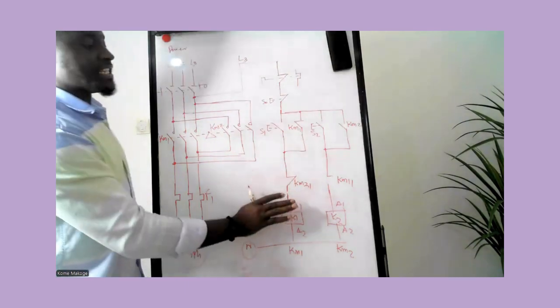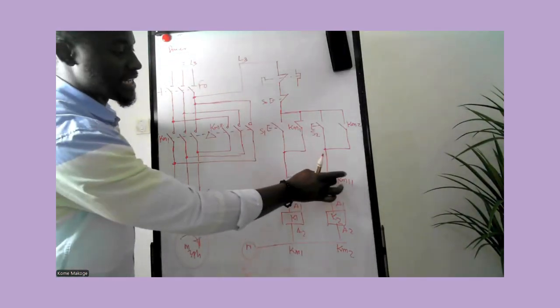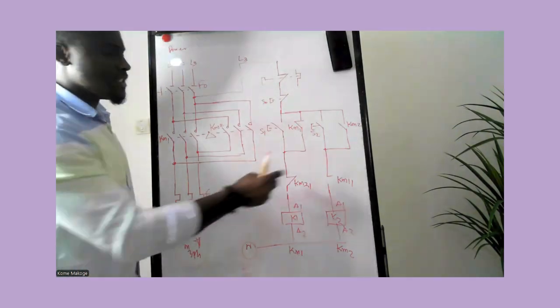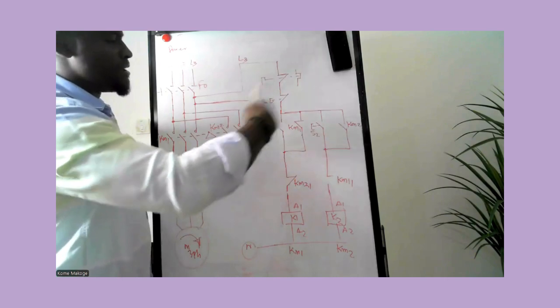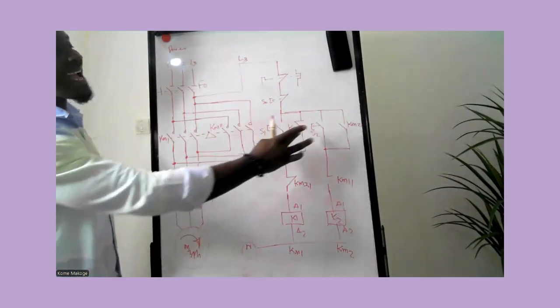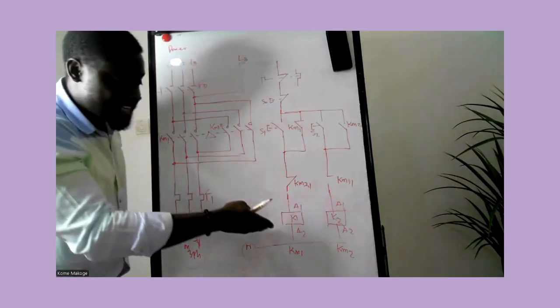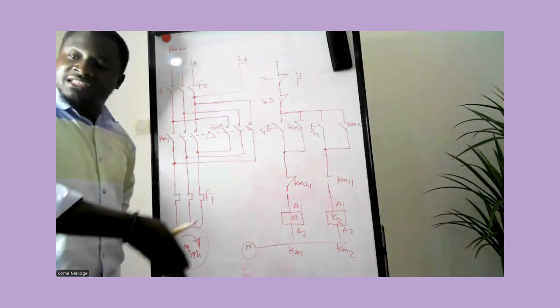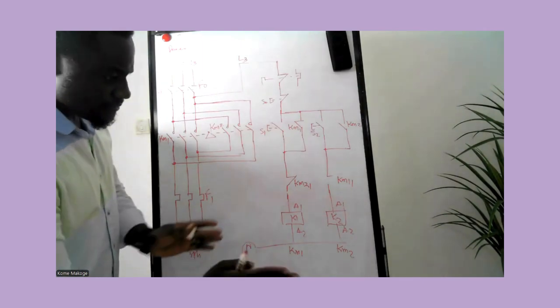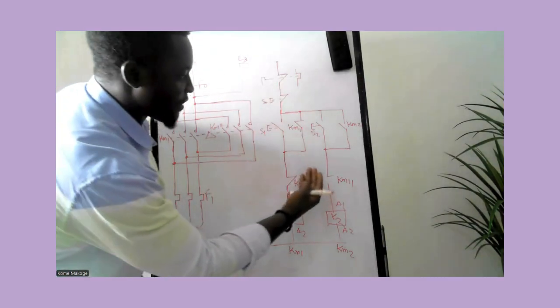This coil remains energized and this contact here is open. The reason we place this KM1 contact in the direction of KM2 is so that if someone tries to energize coil KM2 by pressing start push button S2, it will not allow current to flow from upstream to downstream — because KM1 is already energized and has opened all its associated contacts. This prevents both coils from being energized simultaneously, which would confuse the motor.